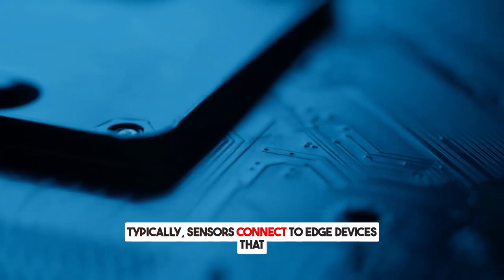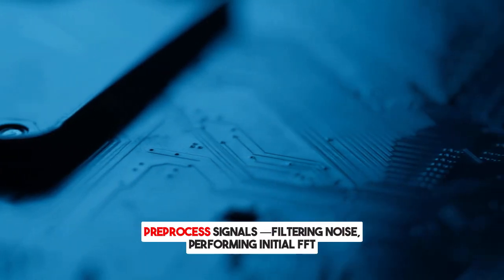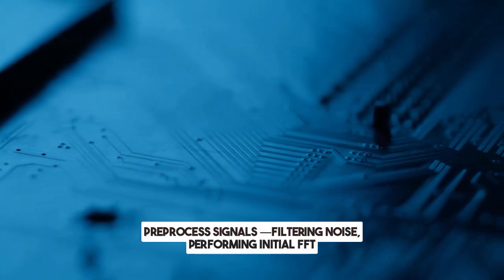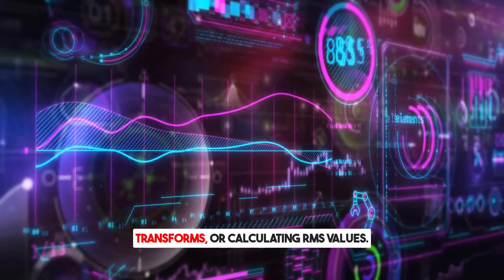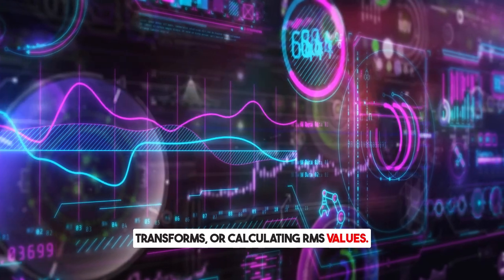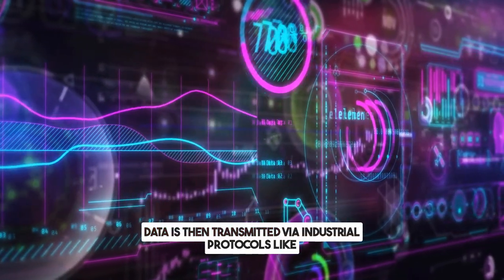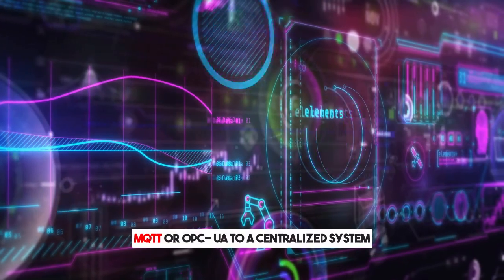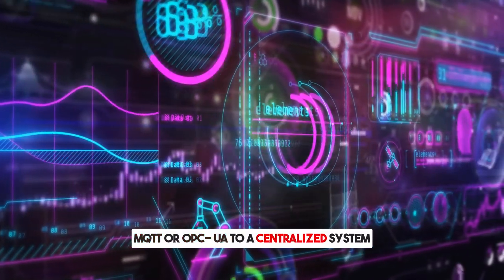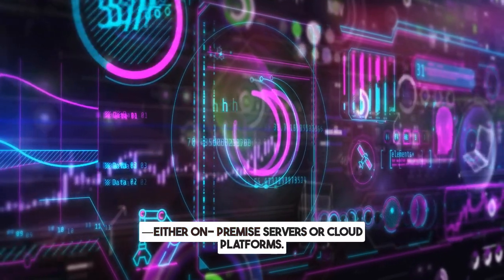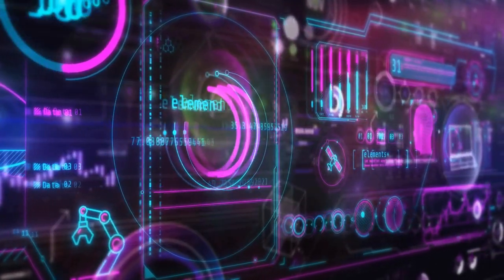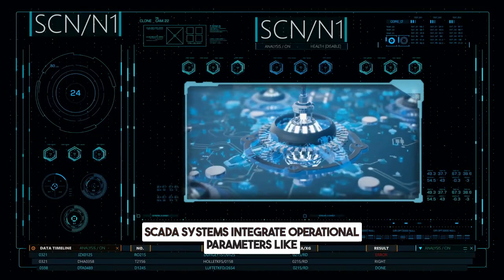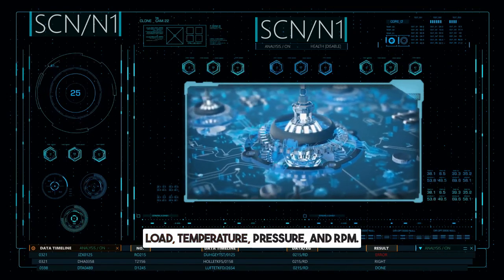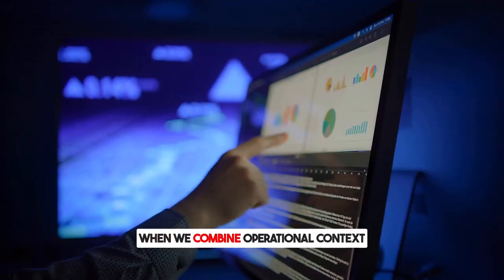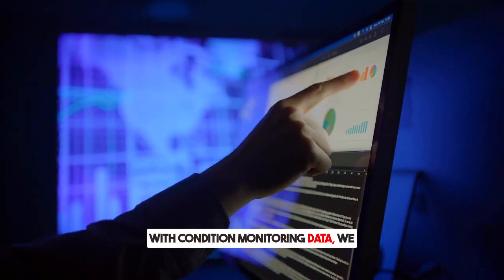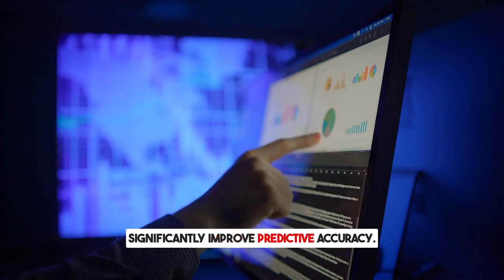Typically, sensors connect to edge devices that preprocess signals, filtering noise, performing initial FFT transforms, or calculating RMS values. Data is then transmitted via industrial protocols like MQTT or OPC UA to a centralized system, either on-premise servers or cloud platforms. SCADA systems integrate operational parameters like load, temperature, pressure, and RPM. When we combine operational context with condition monitoring data, we significantly improve predictive accuracy.